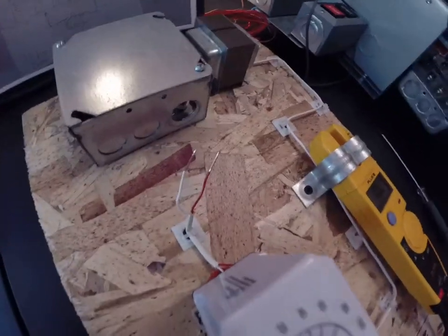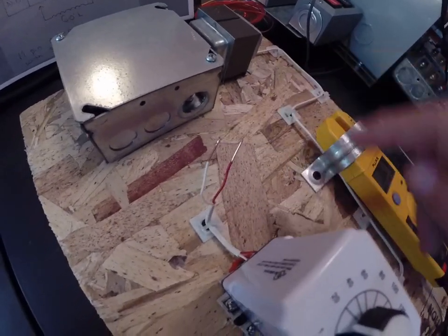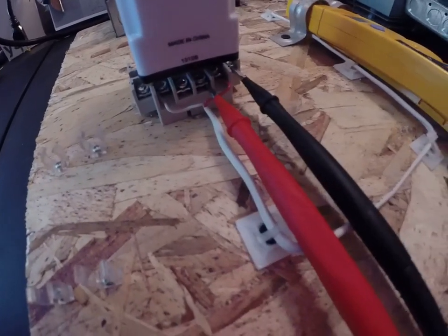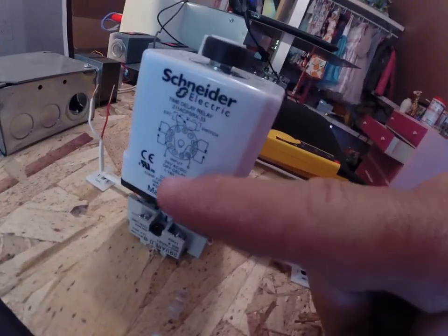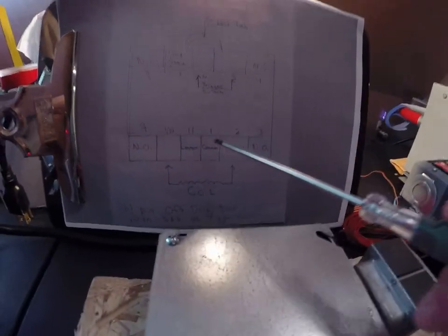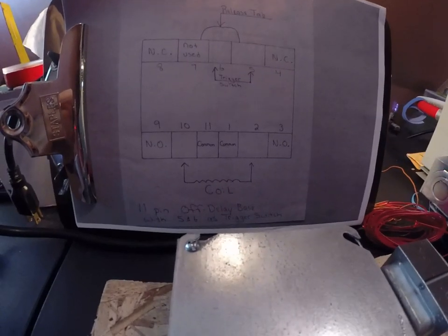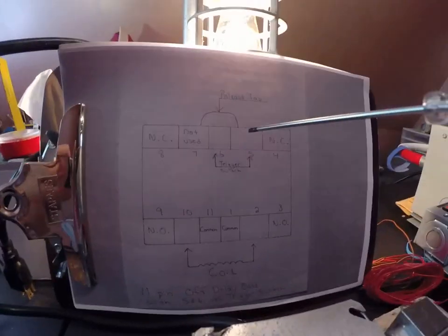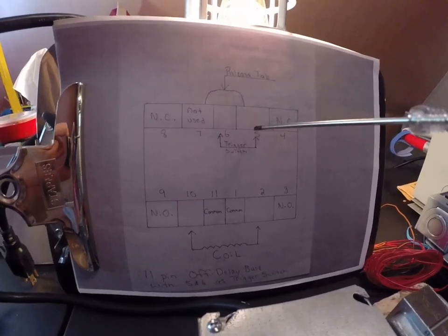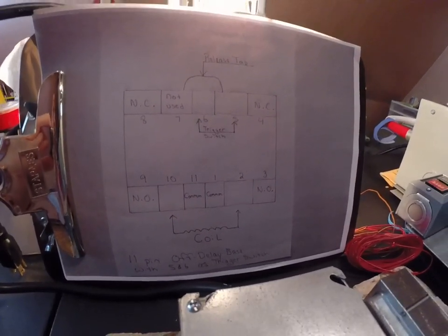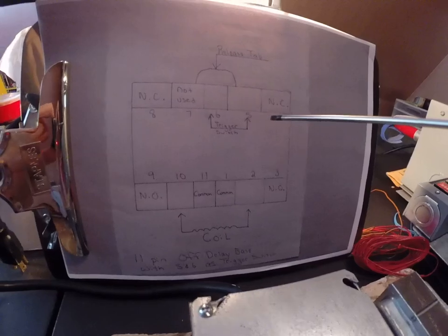So understand two things you learned from this. There's voltage here as soon as you energize the coil. The coil has to be energized at all times on these off delays with trigger switches. Understand that there's a key on this. These only go in one way, so you've got to figure that out. And you're learning another base. You've got 11 screws on this base. You've got to know what they do. If you accidentally put an outside voltage to 5 and 6, you'll ruin the circuit board in there that creates that trigger switch because there's already voltage there.